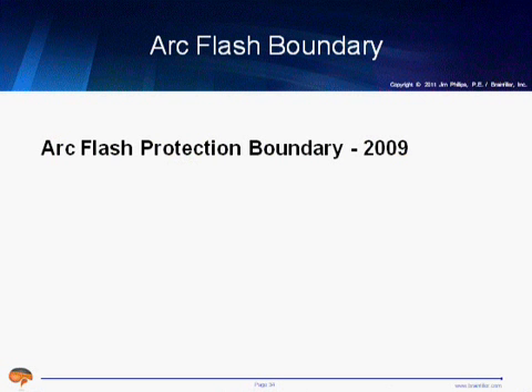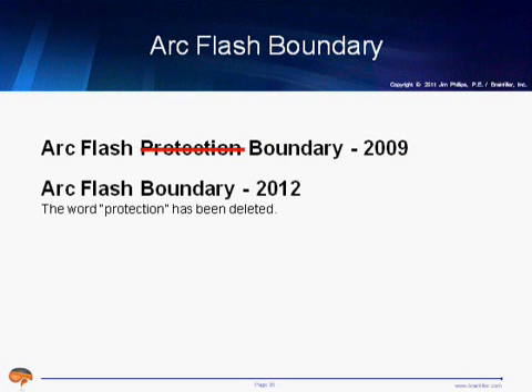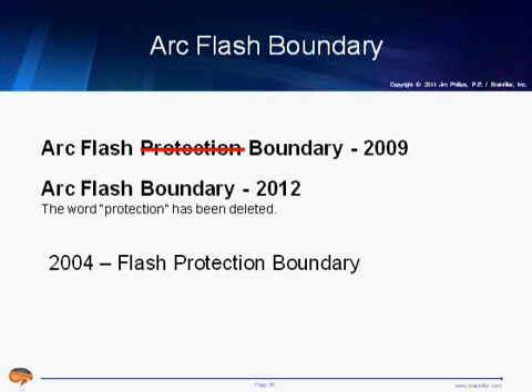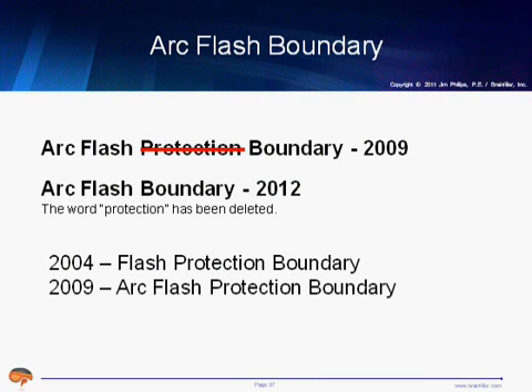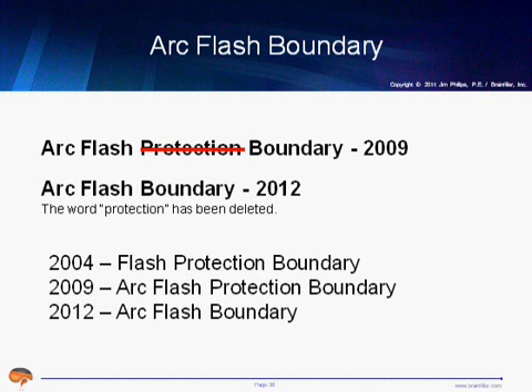The arc flash boundary has changed, the terminology again. This was arc flash protection boundary back in 2009. But there was a proposal that recognized that you have the limited approach boundary, the restricted approach boundary, and the prohibited approach boundary. And in all those other boundaries, they don't use the word protection. And so beginning in 2012, the word protection is going to be removed, and it's just going to be the arc flash boundary. So if you've followed this over the years, some of the evolution: in 2004, this was called the flash protection boundary. And then in 2009, it became the arc flash protection boundary, and now in 2012, it's going to be the arc flash boundary.